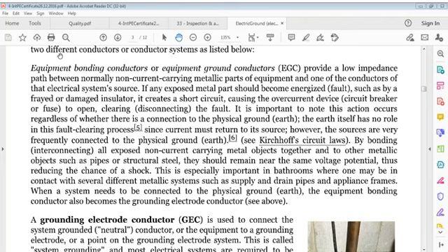And by bonding, interconnecting, all exposed non-current carrying metal objects together and to other metallic objects such as pipes or structural steel, they should remain near the same voltage potential, thus reducing the chance of a shock. This is especially important in bathrooms where one may be in contact with several different metallic systems, such as supply and drain pipes and appliance frames. When a system needs to be connected to physical ground or earth, the equipment bonding conductor also becomes the grounding electrode conductor.